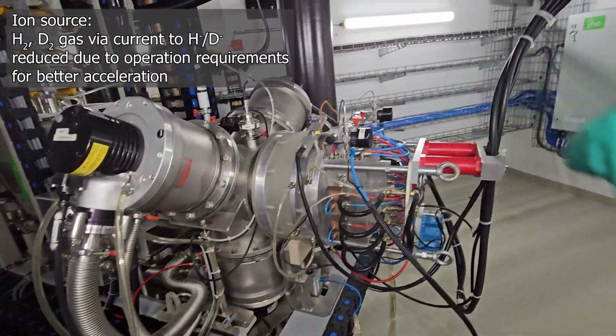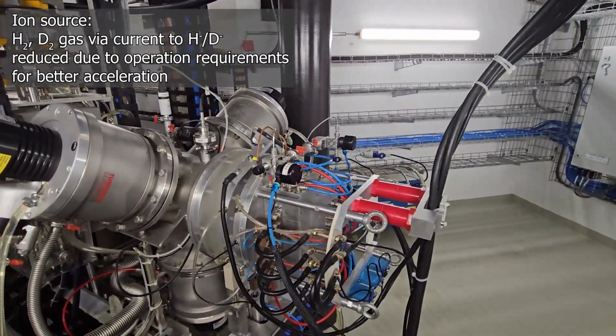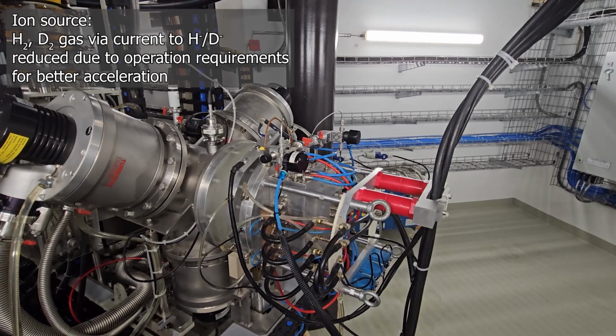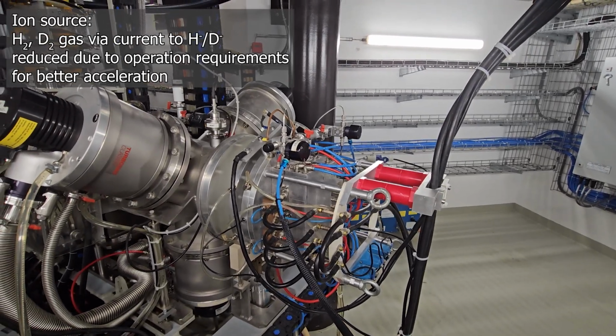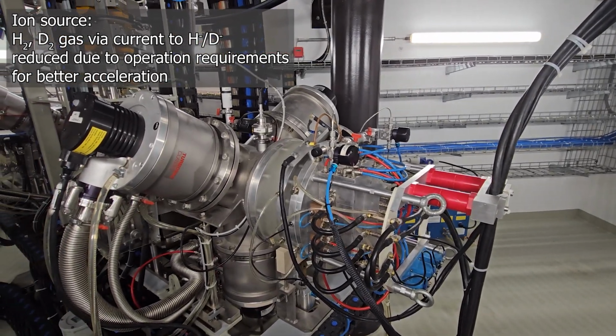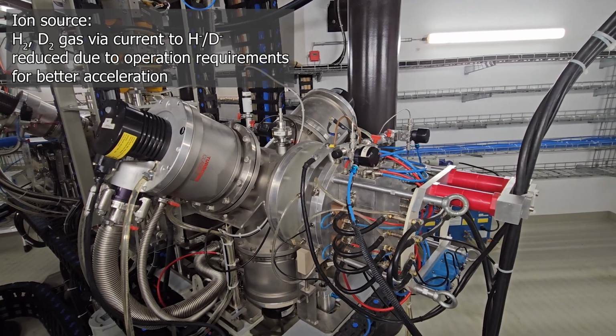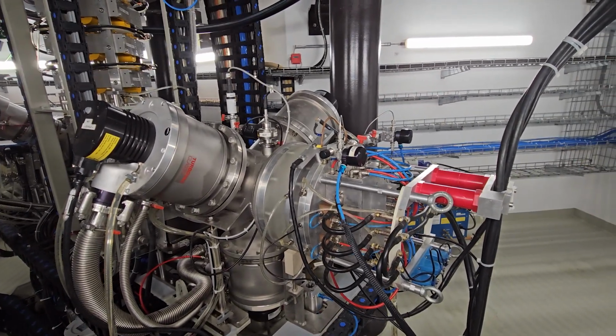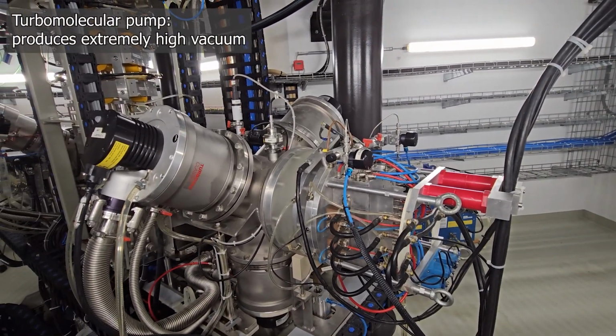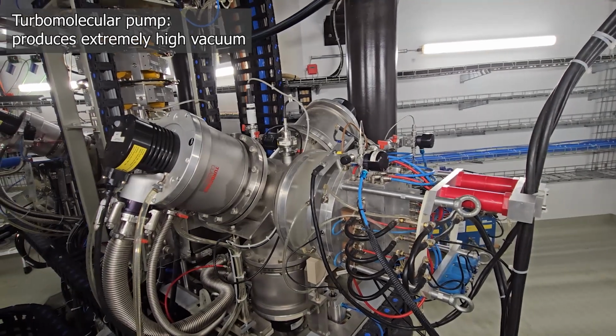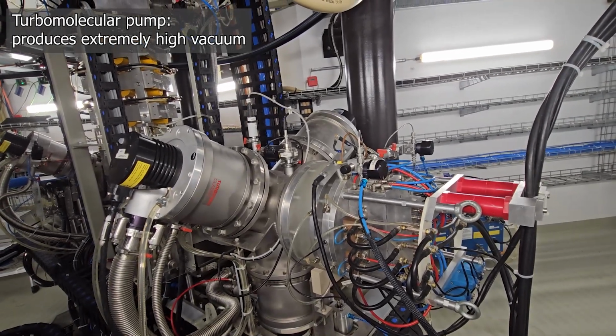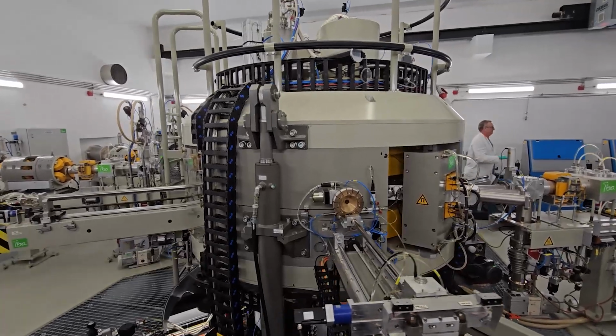On the other side, there is another ion source for deuterium and hydrogen. So again, H2 gas or D2 gas is used. Electrons are added and then you will end up with H- or D- for acceleration. These three cylinders are turbomolecular pumps. The ions are transported via a beamline into the center of the machine. This is where the actual acceleration happens.